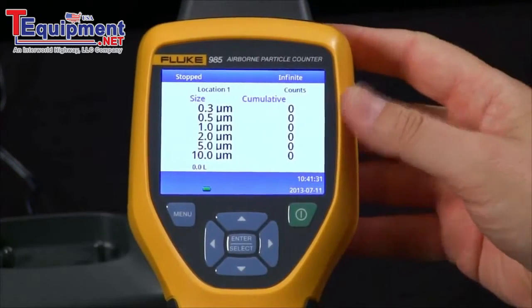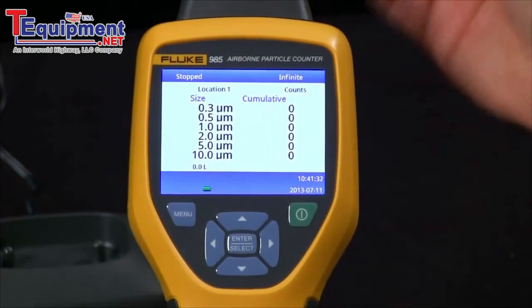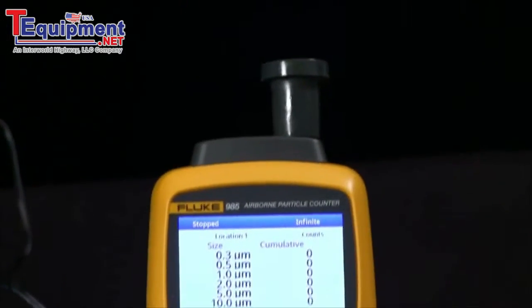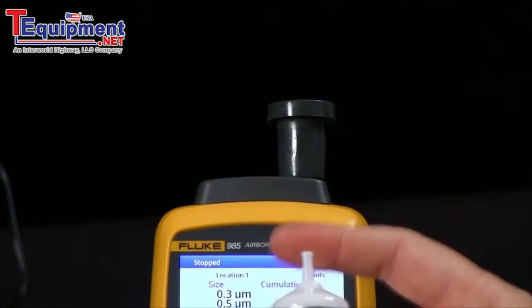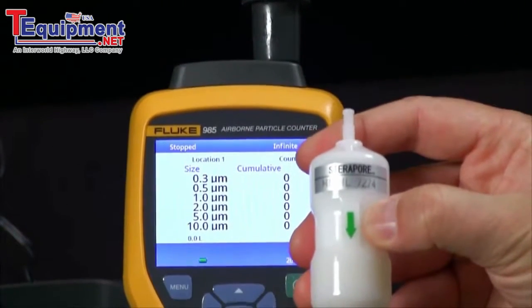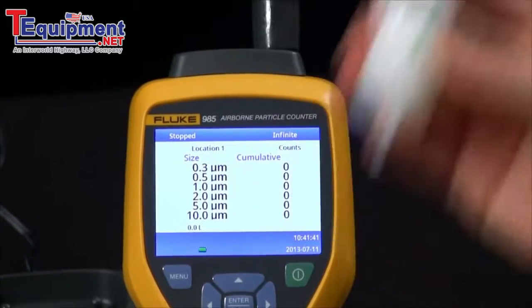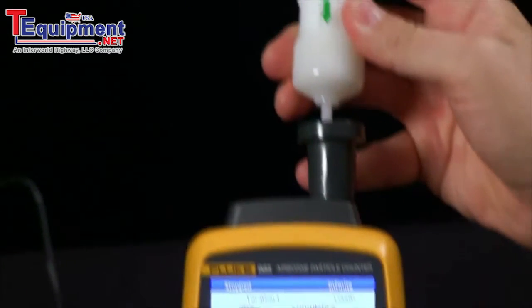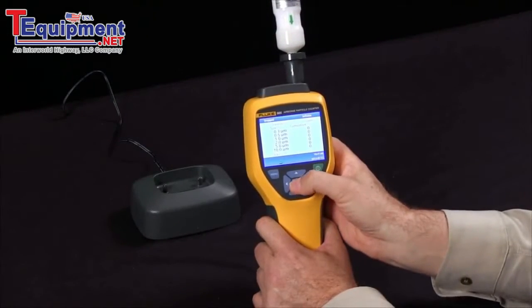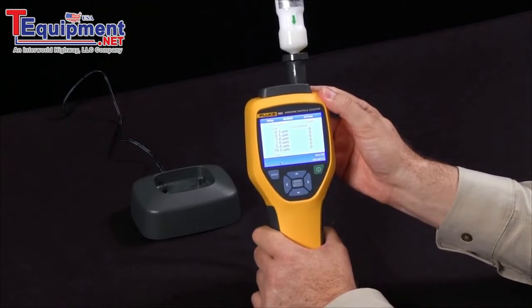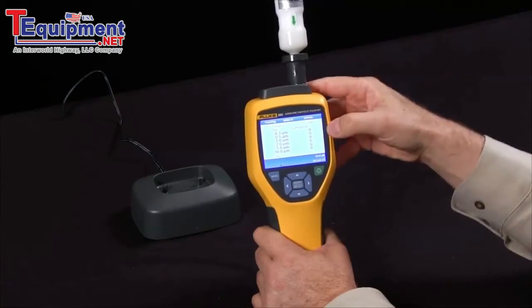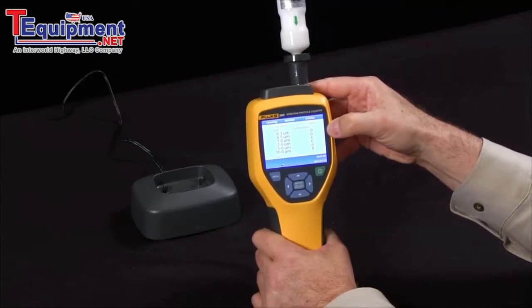To establish a baseline, we provide an adapter which goes over the sample port, and a zero pass filter. You will see the direction of airflow is indicated by the green arrow. Simply insert this into the adapter, start your sample, and if the filter is working properly, we should see next to nothing coming through on the particulate counter.